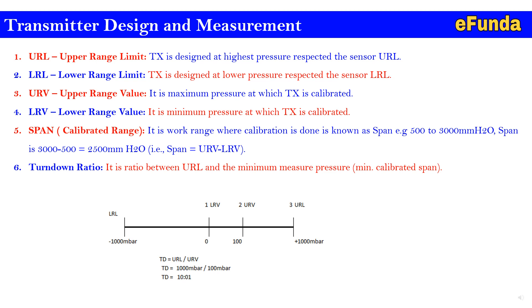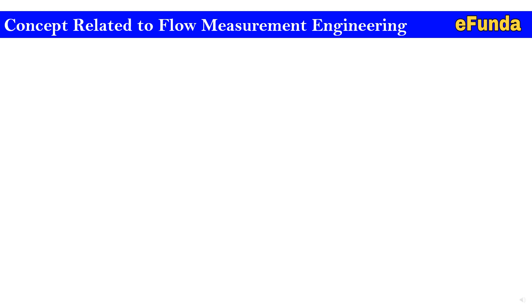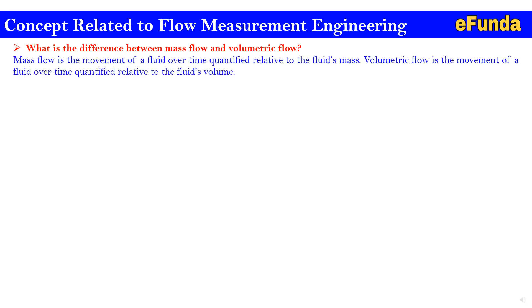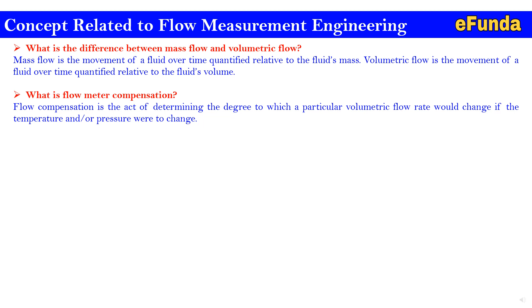After calculating with those values, the turndown ratio comes as 10:1. Regarding concepts related to flow measurement engineering: what is the difference between mass flow and volumetric flow? Mass flow is the movement of a fluid over time quantified relative to the fluid's mass, while volumetric flow is quantified relative to the fluid's volume. Flow compensation is the act of determining the degree to which a particular volumetric flow rate would change if there is a change in temperature or pressure.